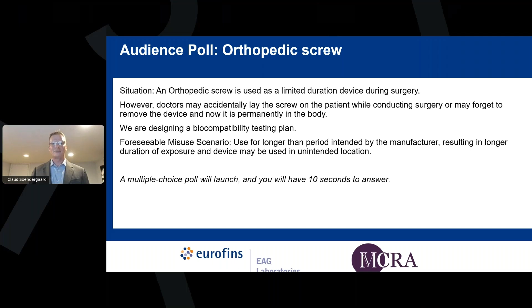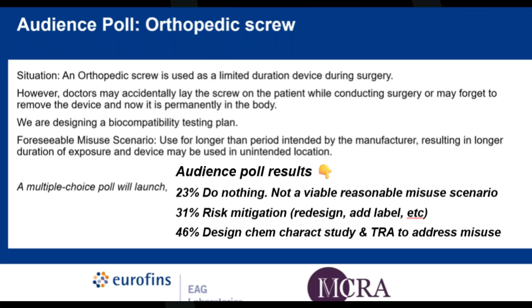So the situation is, an orthopedic screw is used as a limited duration device during surgery. However, doctors may accidentally lay the screw on the patient while conducting surgery, or may forget to remove the device, and now it is permanently in the body. We are designing a biocompatibility testing plan. The foreseeable misuse scenario is use for longer than the period intended by the manufacturer, resulting in longer duration of exposure, and the device may be used in an unintended location. And so now I will launch the poll.